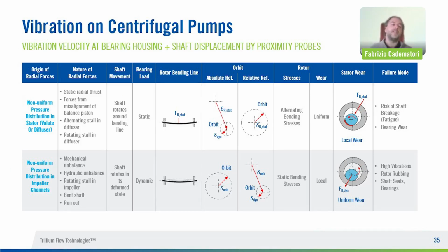Okay. This is a very peculiar part of my discussion, since it's not uncommon that for monitoring a large pump, we have to measure both vibration in terms of velocity of the bearing housing and shaft displacement with proximity probes. Sometimes it is observed that shaft vibration is quite low, whereas bearing housing vibration exceeds the allowable limits considerably. In other cases, shaft vibration exceeds the allowable limits, while bearing housing vibration is quite low.